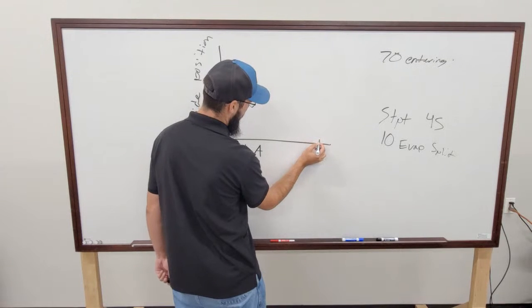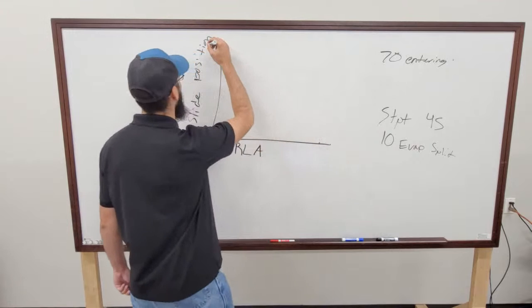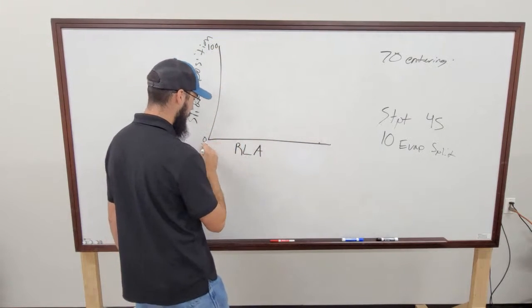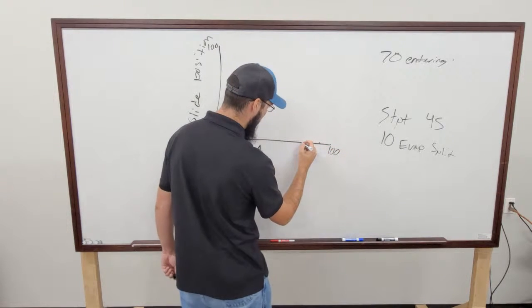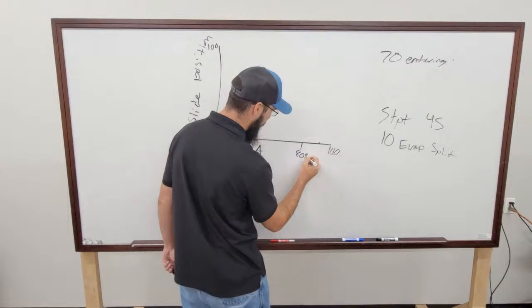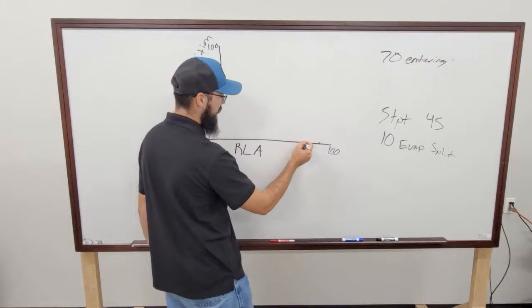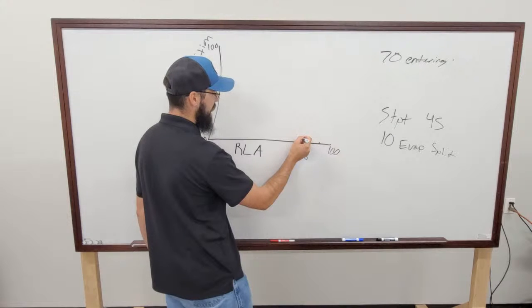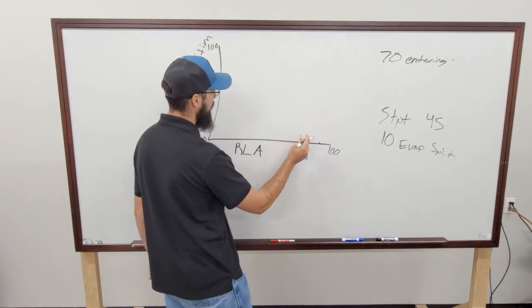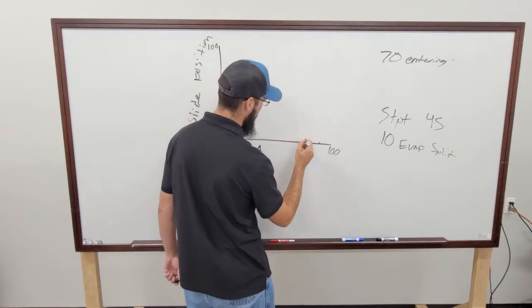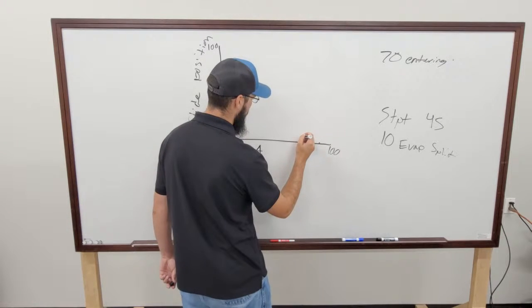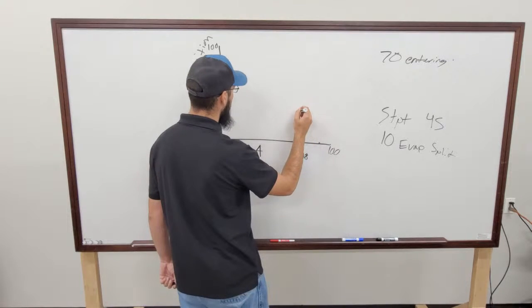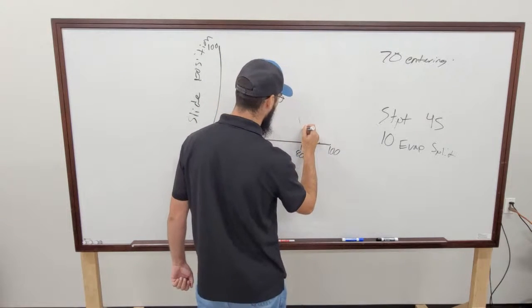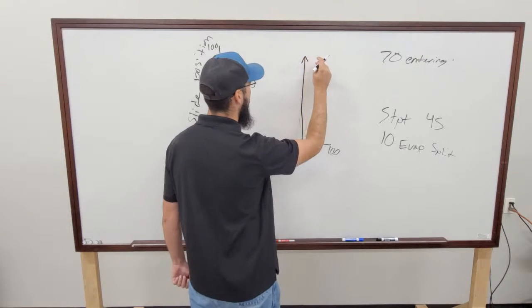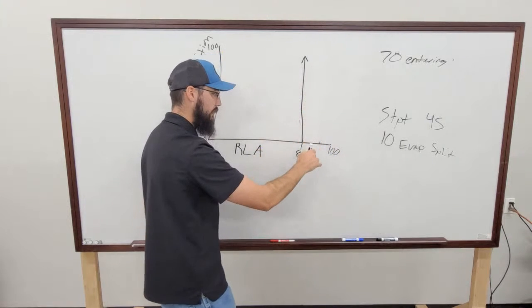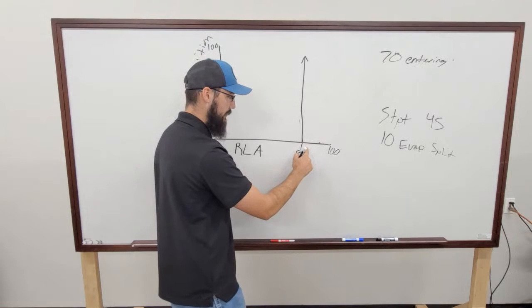Why not put a min and a max on your RLA side? Wouldn't that make it a little easier? So this would be slide position 100%, 0, RLA 0, RLA 100. Let's say we had an 80% current limit. So as we pull the water down, I'm trying to picture this in my mind. Our RLA would remain constant. It'd kind of be a straight line. Our slide valve would increase as the water temperatures decrease, but our RLA remains constant.